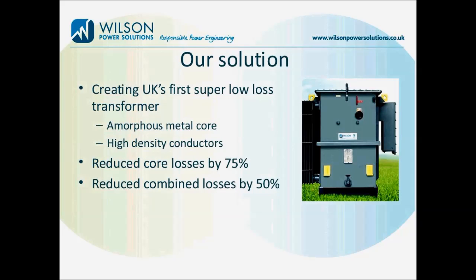What we did was we set out to create the UK's first super low loss transformer. The Wilson E2 is the first distribution transformer in the UK to combine two energy efficiency approaches, combining amorphous metal cores with low current density conductors. The unit's losses are reduced by up to 75% in the core, and as a rough guide, overall transformer losses are cut in half, making the E2 the most energy efficient transformer available in the UK.